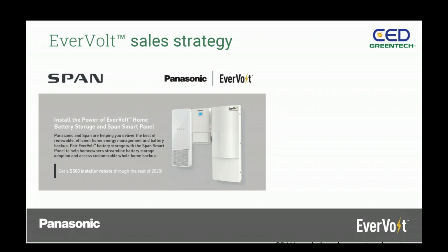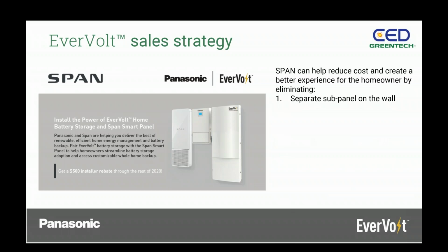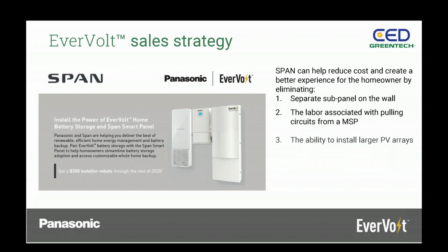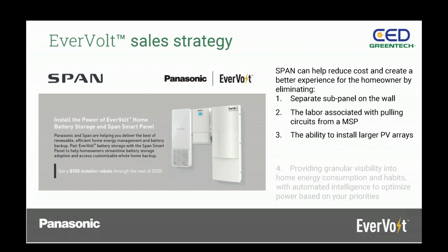There are additional benefits too. What does Span eliminate? It eliminates a separate essential loads panel on the wall—one less thing to put up, one less thing to worry about. It also eliminates the labor of pulling circuits from a main service panel to a sub panel, which can sometimes be very difficult, crawling through crevices. It also allows the ability to install larger PV arrays, since sizing limitations get thrown away—if you have separate circuits for multiple PV inverters or microinverters, you can simply shed some of those during an outage.